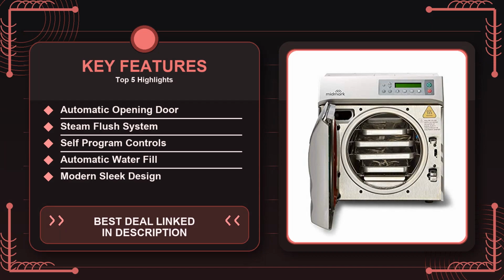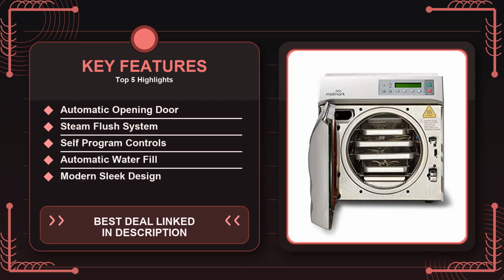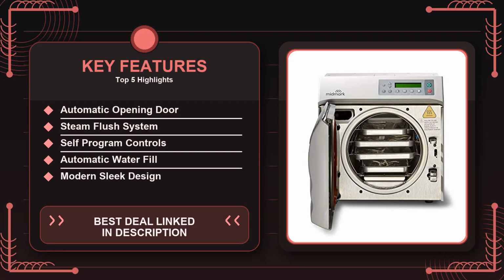First off, the biggest draw is the automatic opening door. In theory, that means after a cycle finishes, the door pops open on its own, letting the steam escape and exposing the interior to air, an important step for preventing moisture buildup and for making it easier to remove delicate items. In practice, the door does open automatically, but it can be a little abrupt. If you're working with fragile instruments or delicate glassware, you might need to brace the door or manually hold it open for a few seconds to make sure nothing gets knocked out. It's not a deal breaker, but it's something to keep in mind if you're sterilizing precision tools.